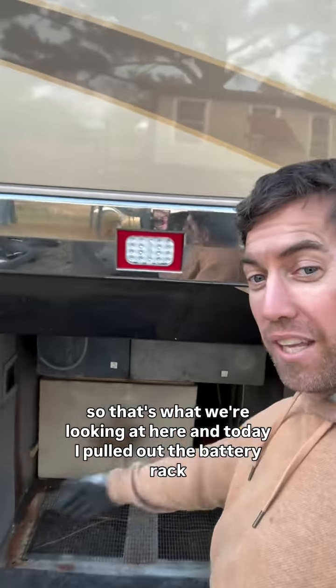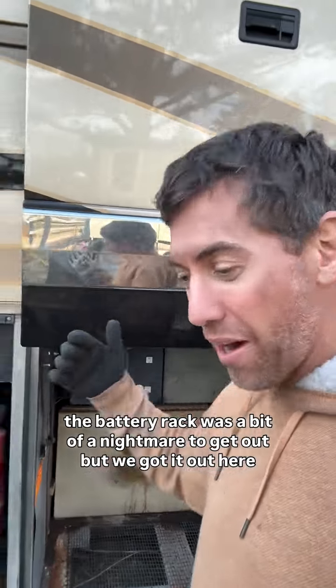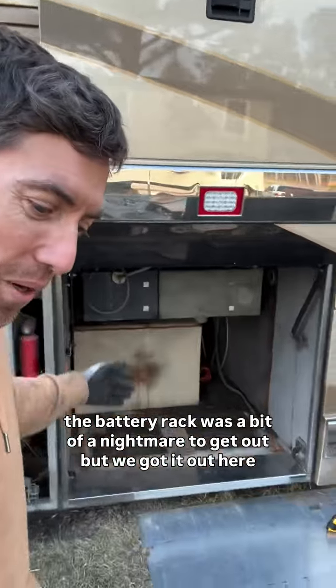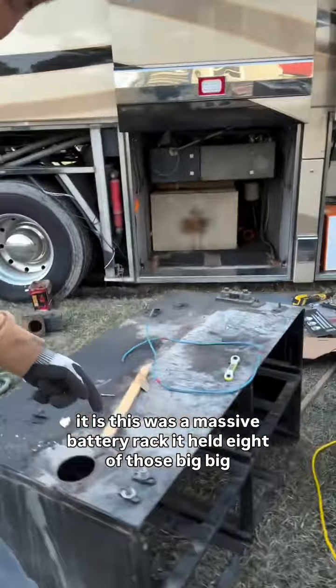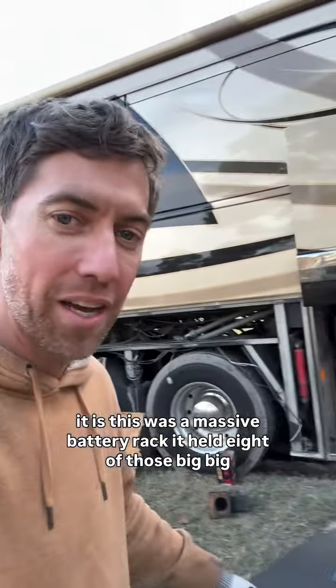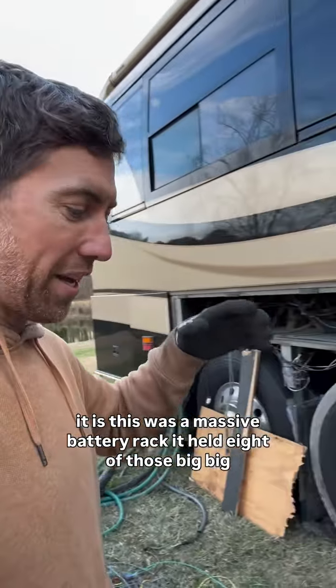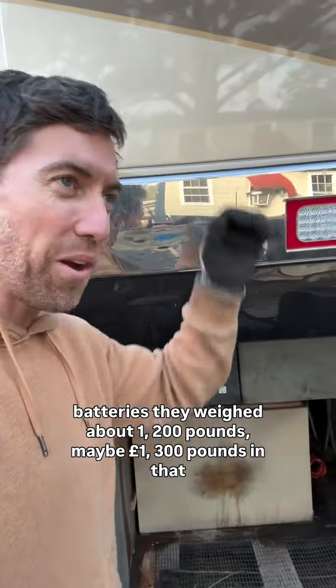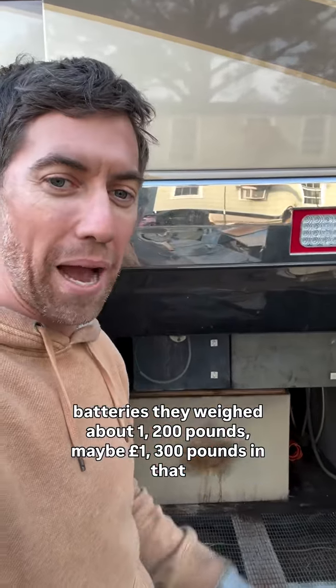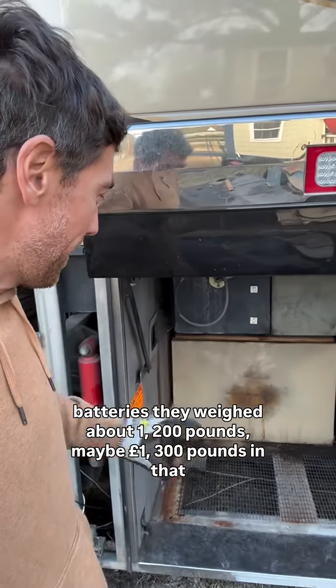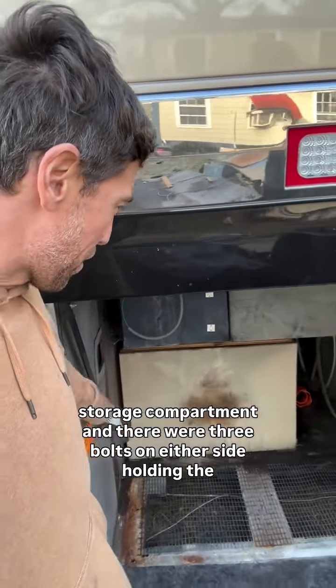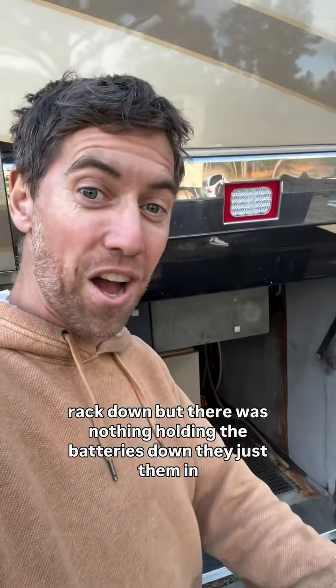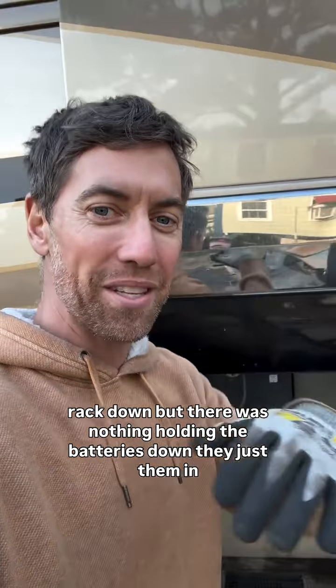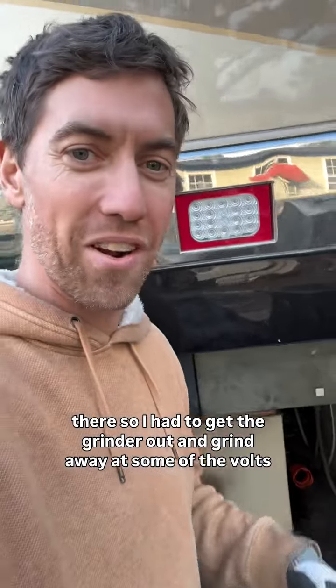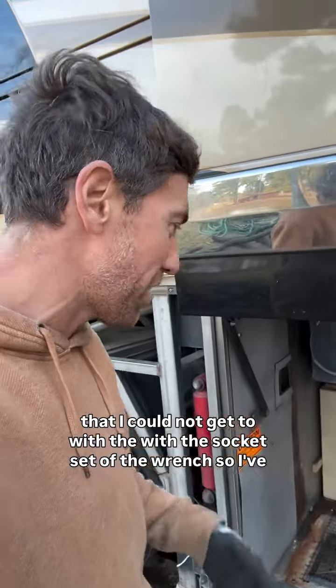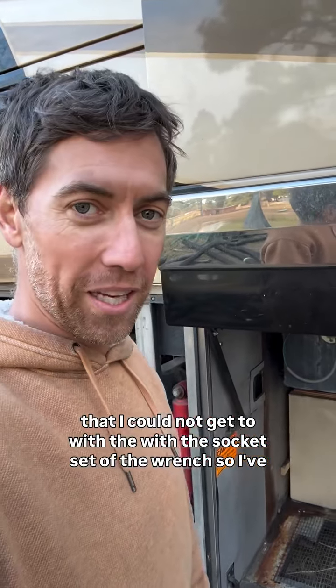Today I pulled out the battery rack. It was a bit of a nightmare to get out, but we got it out. Here it is—this was a massive battery rack that held 8 of those big batteries, weighing about 1,200 to 1,300 pounds in that storage compartment. There were 3 bolts on either side holding the rack down, but nothing holding the batteries themselves—they just put them in there. So I had to get the grinder out and grind away at some of the bolts I couldn't reach with the socket set or wrench.